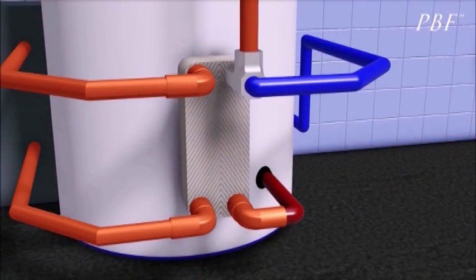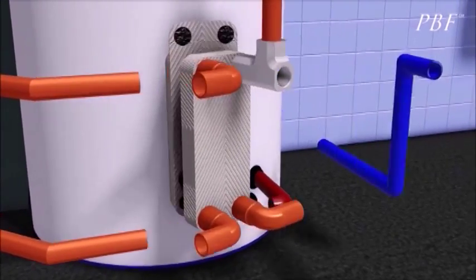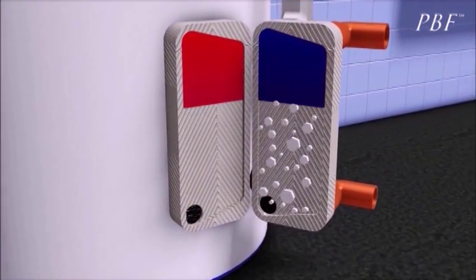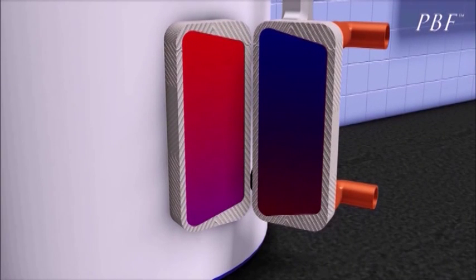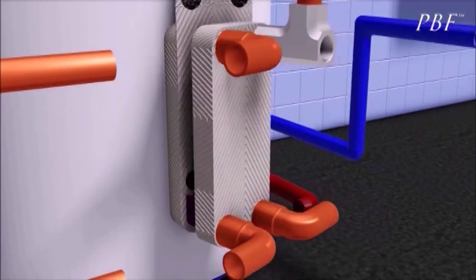No hot water, cold showers. Exactly, which is the tagline we're using: no more cold showers. So what our technology does is incredibly simple. Every time you turn on your hot water to use it, instead of the incoming cold mains water simply going into the bottom of your storage tank as it does now, we divert that water and put it back through the heat exchanger. That change in flow and temperature cleans this buildup of calcium carbonate and other minerals, redissolves them, and flushes them back into the tank, where we happily drink them in our water, and it's good for our teeth and bones.